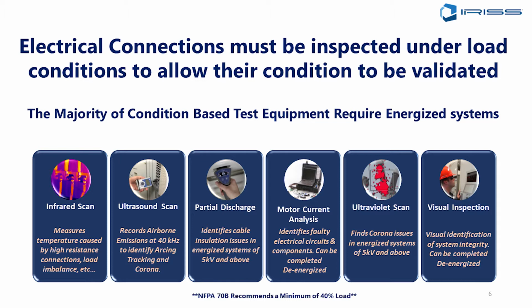Ultrasound allows us to listen for partial discharge type events which give off noise in the ultrasound spectrum above the range of human hearing. Humans can hear up to about 20 kilohertz when you're young. As you get older, that declines. So I'm at about 15, 16 kilohertz right now, and as I get older, it'll go lower and lower. It's the high frequency part of our hearing that we lose first.